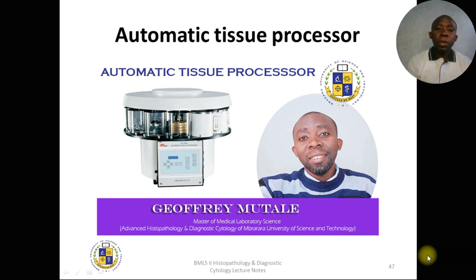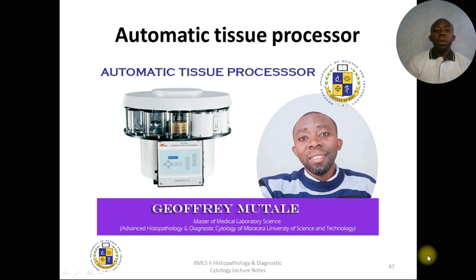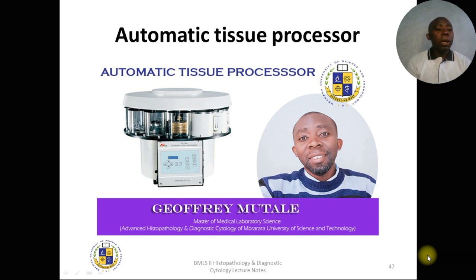In the first type of tissue processor, the tissue in the cassette moves from one bucket to another, taking it through the process. One of the beakers contains formalin for fixation, then the tissue moves to dehydrants — the alcohols — then to xylene for clearing, and finally to an infiltrating agent, which is molten wax.